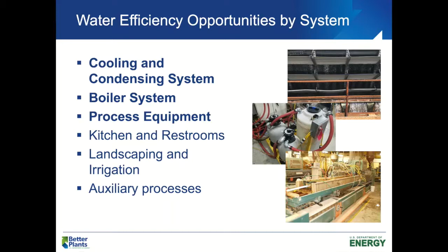A little bit of fundamentals of the cooling tower and how water is used before we go into the opportunities. So we have warm water coming into the cooling tower, which it cools down and sends back to the facility, right? So it removes the heat coming from the chiller or generated at your process equipment. The way it does it is, the warm water coming in gets sprayed on top of the cooling tower, and as it flows down, it comes in contact with air that is coming in the opposite direction, being pulled in through the cooling tower fans. And in this process, the water gets cooled down by the evaporative effect.